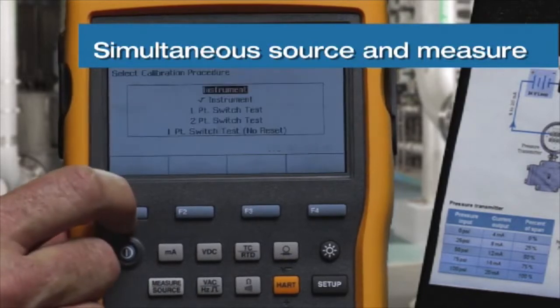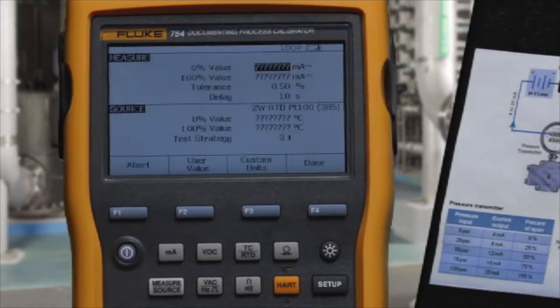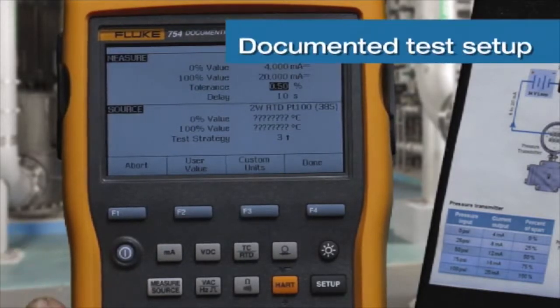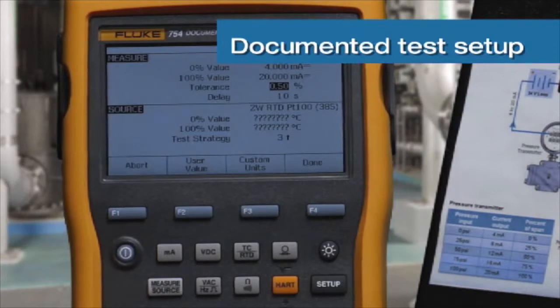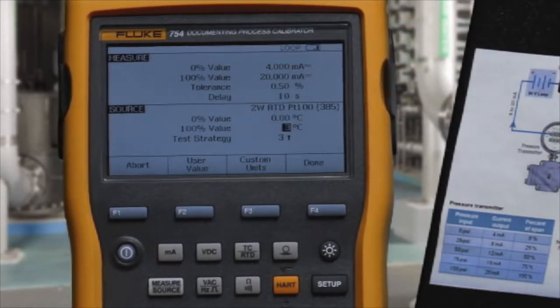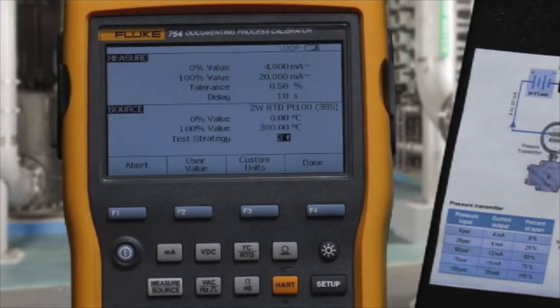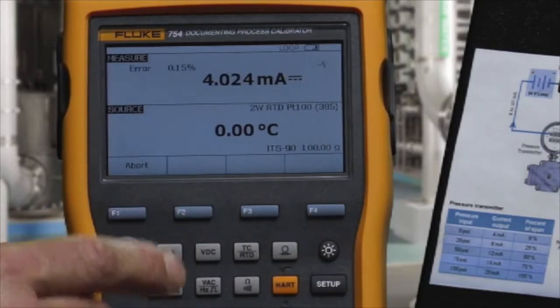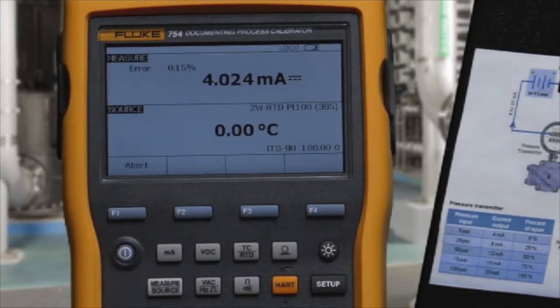We document the calibration as found for an instrument. We're going to measure 4 to 20 milliamps to a test tolerance of 0.5% while sourcing 0 to 300 degrees C. We're going to test three points. Select auto test, and the performance of the transmitter will be recorded.